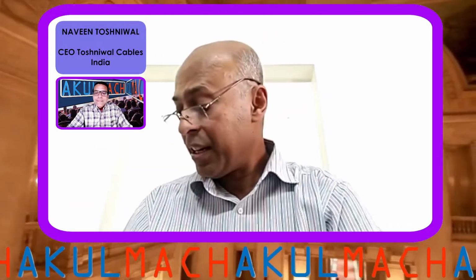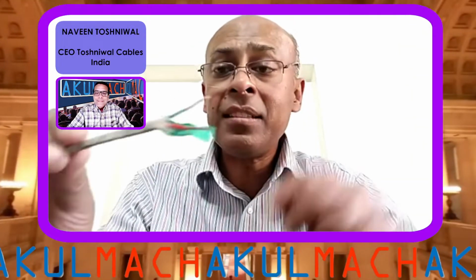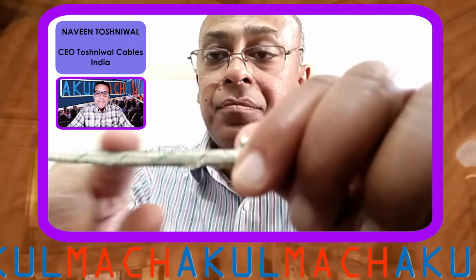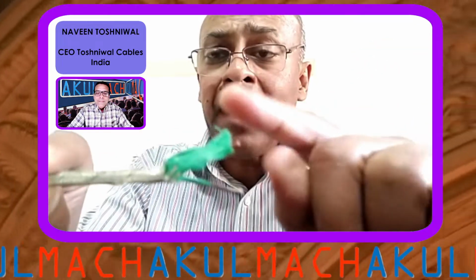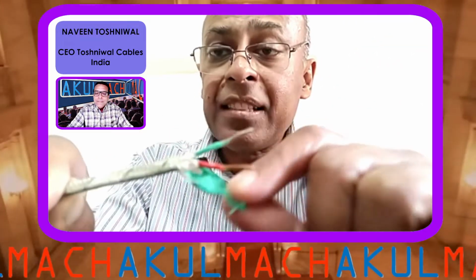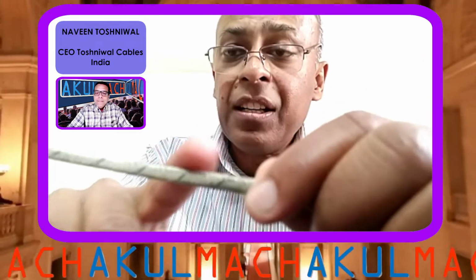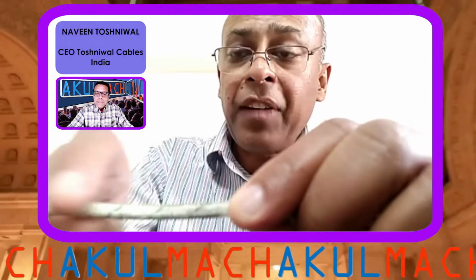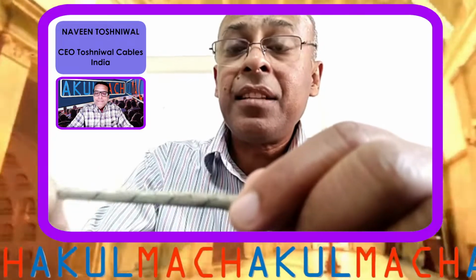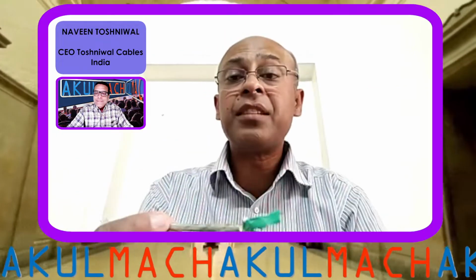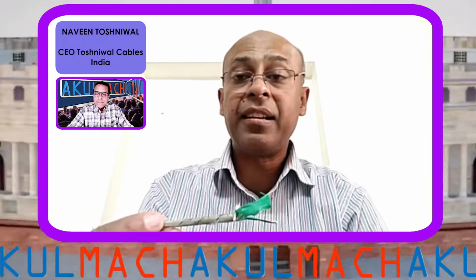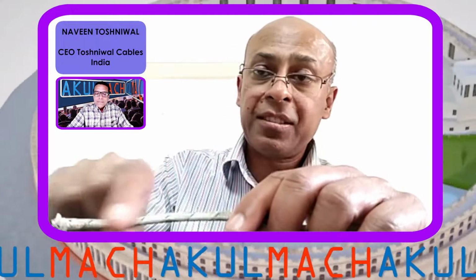Now, there is another type of insulation. See, this is fiberglass. Inside, we have Teflon. This is Teflon core, then there is a Teflon sheath, and then there is an outer sheath of fiberglass. Now, this fiberglass is able to withstand a temperature of maybe 400 degrees centigrade, and we apply a varnish on this. Why the varnish is required?